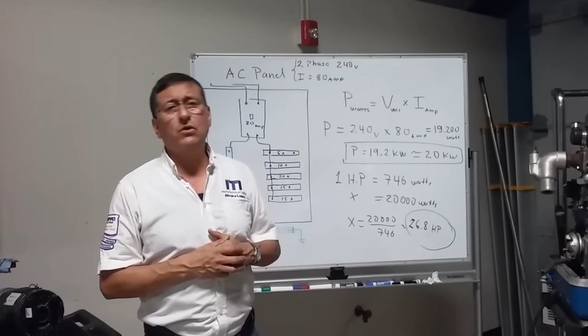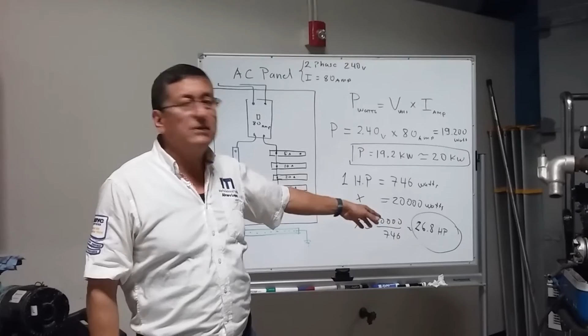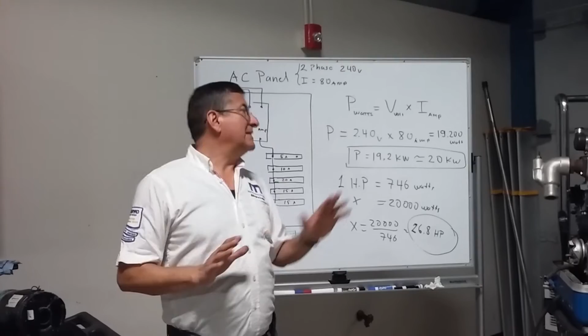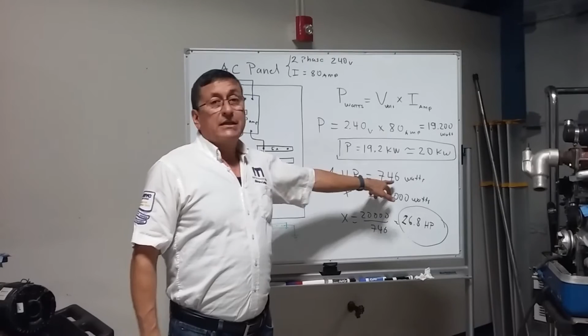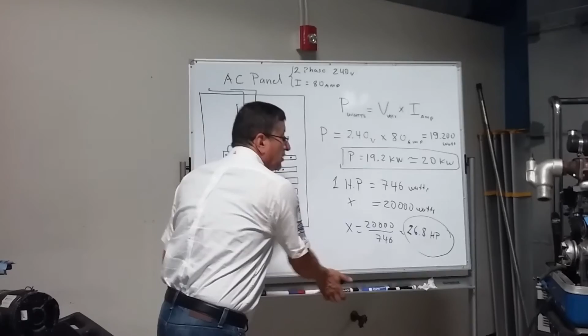Oh, I have an engine of 20 horsepower. Is it good for that generator? No, no, you need a minimum of 27 horsepower. Oh, I have an engine of 30 horsepower. Oh, 30 is perfect. It's a little higher. It's perfect. Okay, this is the procedure to calculate the capacity of the generator in kilowatts and the procedure to convert electrical power into mechanical power. We are going to continue with the next step.